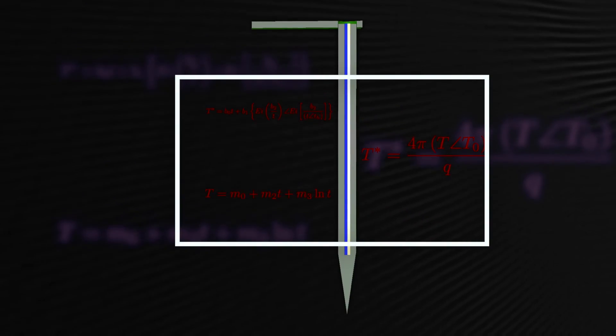Here's how it works. A heater and temperature sensor are housed inside a needle, or in separate needles for thermal diffusivity measurements. Current is passed through the heater and the temperature of the probe is monitored over time. An analysis of the probe temperature is used to calculate thermal conductivity.